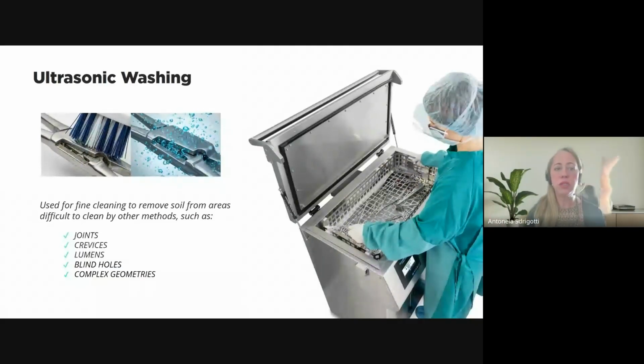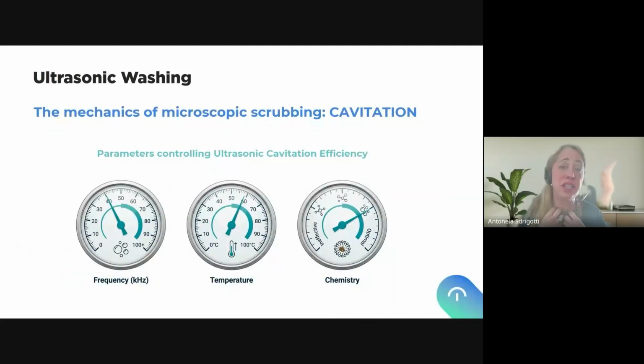As you all know, the ultrasonic washer is used for cleaning and removing soil from areas difficult to clean by other methods, such as joints, crevices, lumens, blind holes, and complex geometries. And the particularity about ultrasonic washing is that the microscopic scrubbing or cleaning is thanks to cavitation.